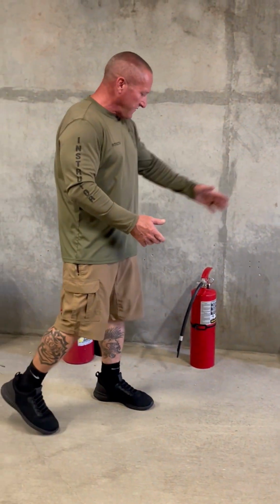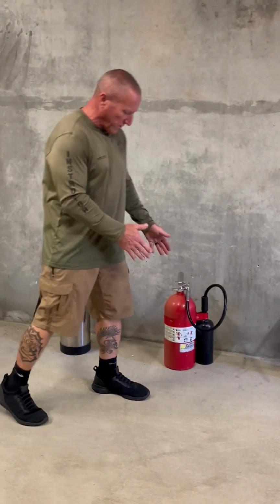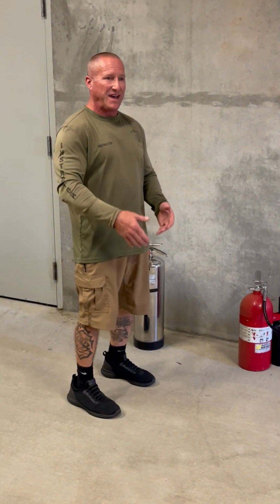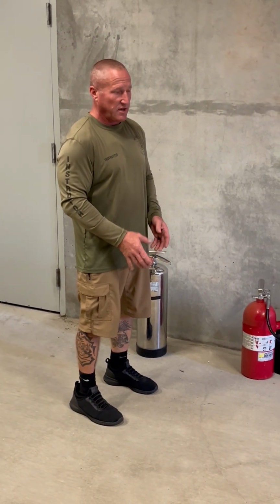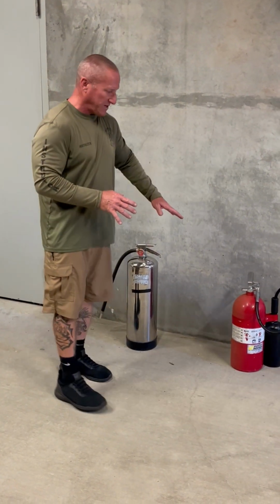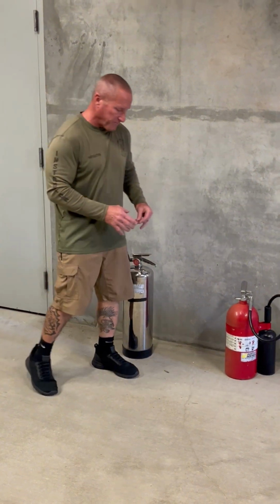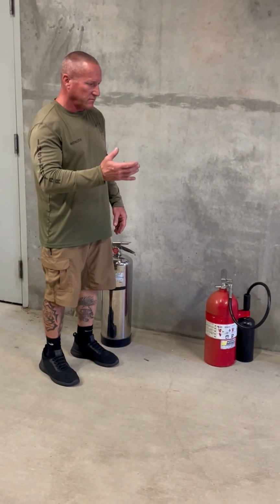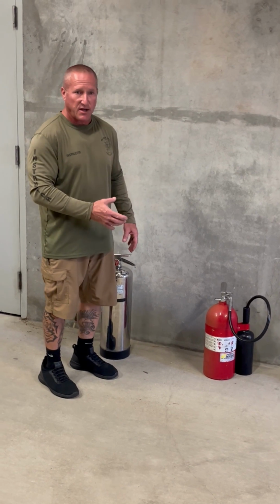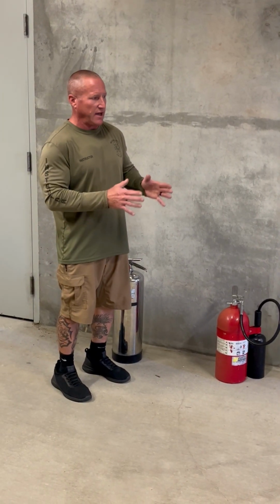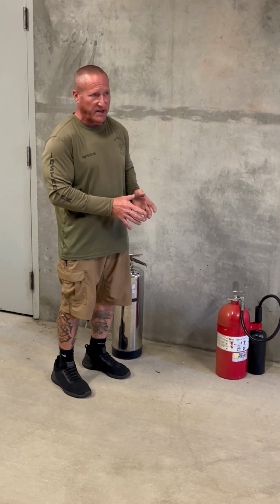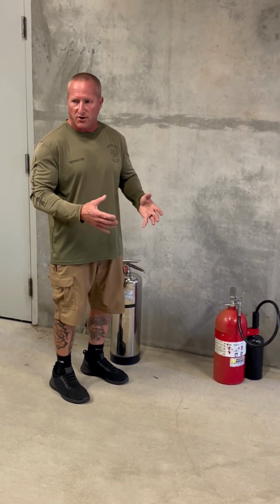When we're done with any of our extinguishers after we've used them, we want to lay them on their side and preferably tag them that they're out of service. The only extinguisher that we don't have here to demonstrate would be basically a clean agent. Clean agents replace the halons. They're used for electrical and for sensitive equipment, basically. It doesn't leave a residue, it doesn't cause much of a problem.